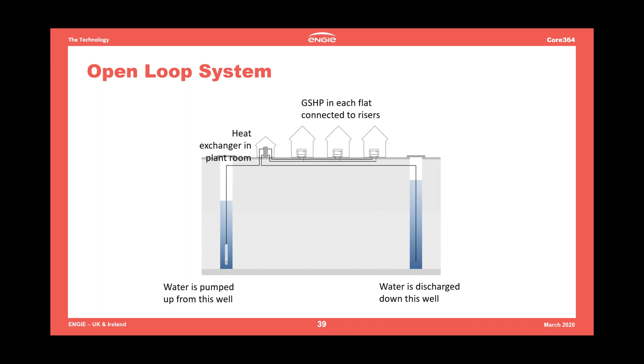On the other side of the plate heat exchanger in the plant room, we just have our riser pipework that's filled with a mixture of water and antifreeze, and that riser pipework is then just rising up each tower block, and then it branches off each floor to serve the flats on each floor. And then in each flat, there's an individual Kensa ground source heat pump providing the heating and hot water. That heat pump is connected to the tenant's own electricity supply, so that they just pay for their energy bills directly to their utility company. And just to the next slide, please, Andrew.